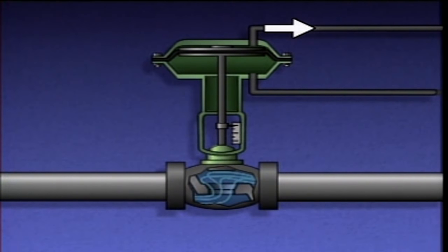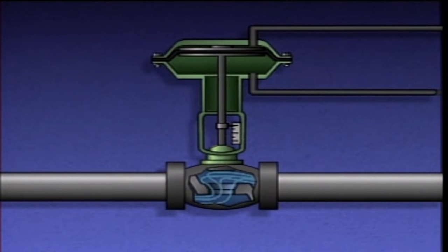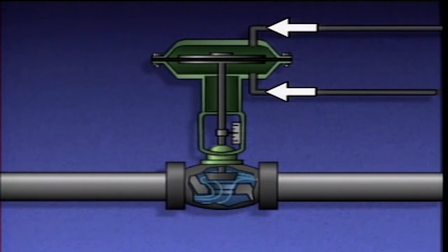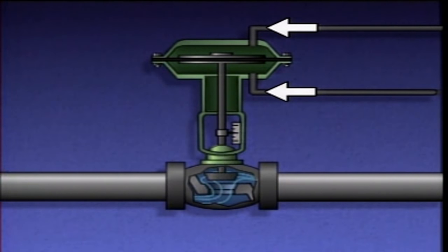Air in the upper chamber is exhausted through the upper air supply port. These actions make stem movement, and therefore valve position, proportional to the difference between the two air pressures applied to the chambers of the actuator.